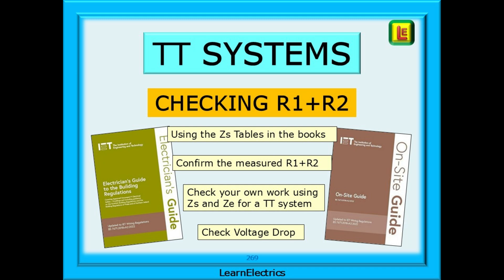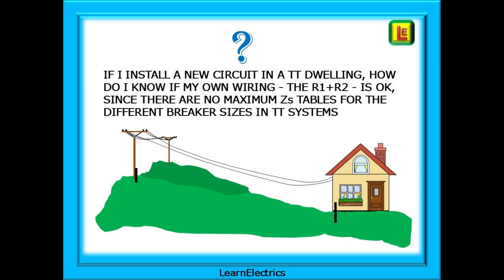We can use the on-site guide or the electrician's guide to the building regulations, since they both contain maximum Zs tables, and page numbers given relate to Amendment 2 of both books. This was the sort of question that was asked. If I install a new circuit in a TT dwelling, how do I know if my own wiring, the R1 plus R2, is OK, since there are no maximum ZS tables for the different breaker sizes in TT systems?